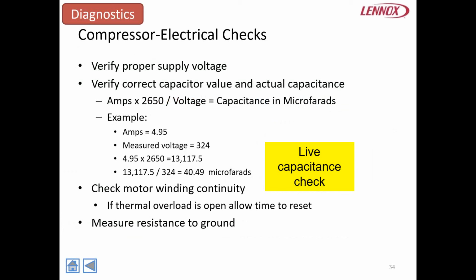I've got a Subco tester that you can actually clip on to a capacitor, and it sends a 9-volt charge out and sends a reading back and says capacitor is reading X microfarads. And it's fairly accurate overall, but if you start doing a live test on this equipment, you'll find, in anybody's equipment, as far as tune-up goes, how many times has a technician gone out in the spring and said the capacitor's good, and by July, August, it's failed? So what happened? Well, was it close or not close?